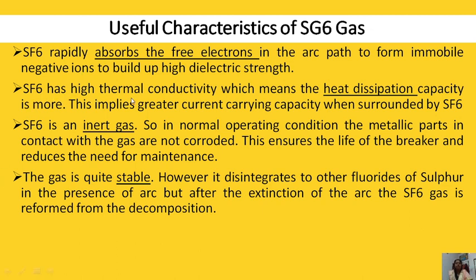SF6 gas has high thermal conductivity, which means its heat dissipation capacity is more. This implies greater current capacity when the contacts are surrounded by SF6. As it is an inert gas, in normal conditions the metallic parts in contact with the gas are not corroded. So the breaker contacts will not get corroded, which ensures the life of the breaker and reduces the need for maintenance.